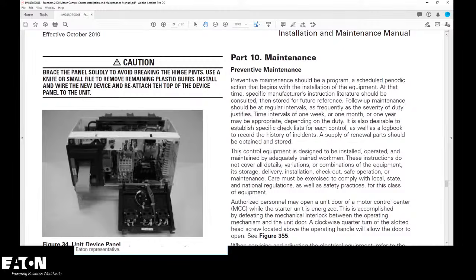It should be a program, a scheduled periodic action that begins with the installation of the equipment. At that time, you have to follow the manufacturer's instructions and store those for future reference. It says follow-up maintenance should be at regular intervals as frequently as the severity of the duty justifies. And that, I would think, would be the conditions you're in for a motor control center: the environment, and probably how often it's being used or cycled or whatnot.